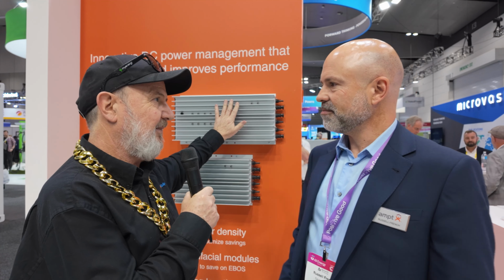So you're effectively putting the battery onto the PV. Well, there are different architectures. In a battery-centric architecture, the battery dictates the DC bus and everything follows the battery, which is a really stable source of voltage, so we just follow the battery. That's incredibly responsive for communications and really stable on the DC bus. Actually, reverse DC coupled or battery-centric architecture comes from telecommunications from the 80s or 90s.